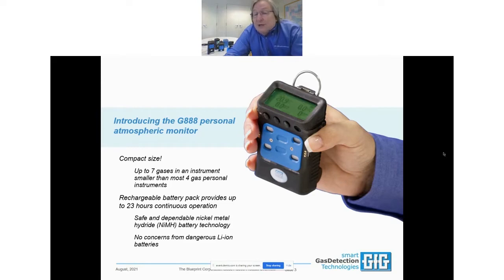It's hard to believe we can dependably measure up to 7 channels of hazard at the same time—CO2, IR, catalytic LEL, all sorts of different toxic sensors, including dual-channel COSH sensors for CO and H2S measurement. We're not stuck using a COSH sensor; we can use individual single-channel sensors for CO and H2S measurement, which has a lot of advantages. So really, really flexible.